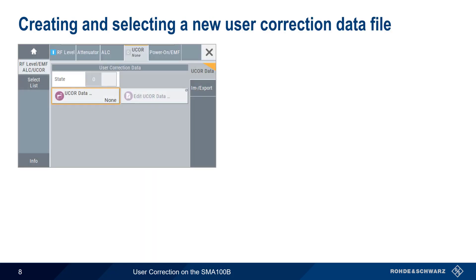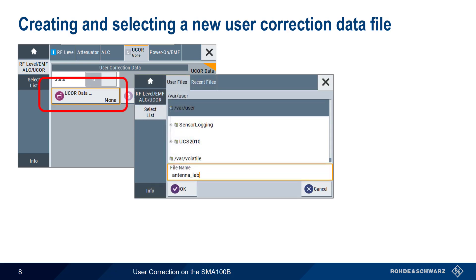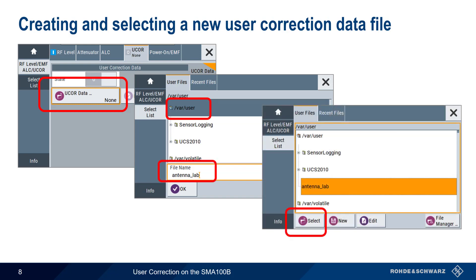The first step in creating user correction data is creating a new empty user correction data file. Click on UCOR Data and choose a path and file name for the user correction data file. After creating the file, highlight and select it before returning to the User Correction menu.